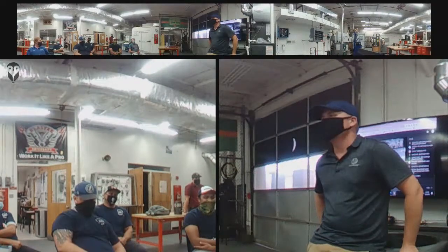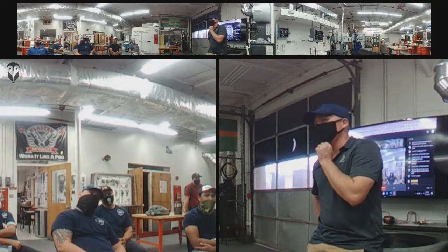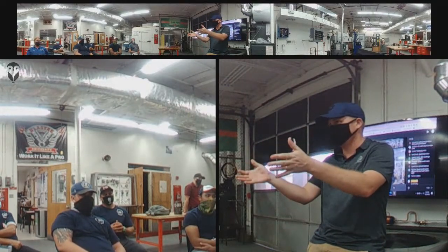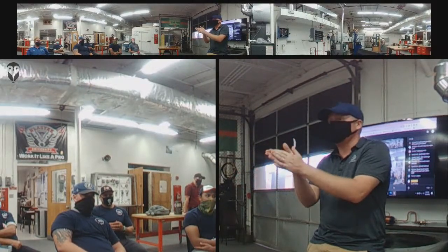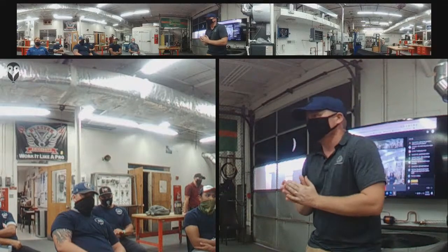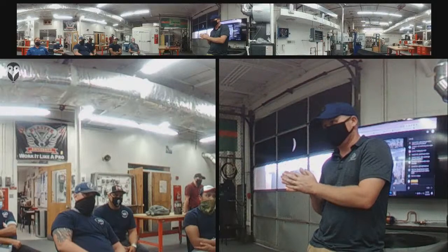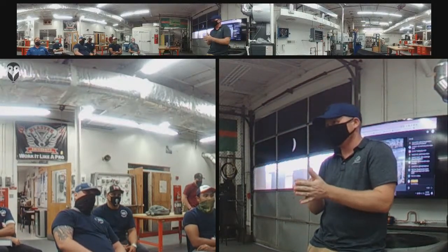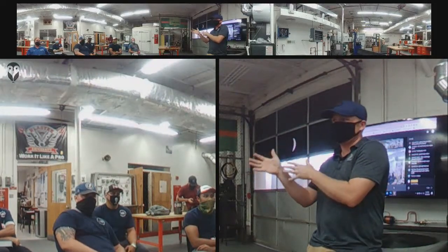So one thing to always look for, though: this was a commercial unit, I assume, right? Yeah, it's a two-stage package. Two-stage package, okay. On commercial equipment, when you're in a commercial building, you always want to check how the transformer is tapped, like we talked about. If that transformer is tapped for 240 and you have 208, or 230 and you have 208, then that can cause you to have lower than designed voltage.